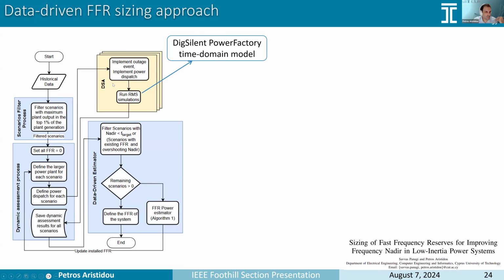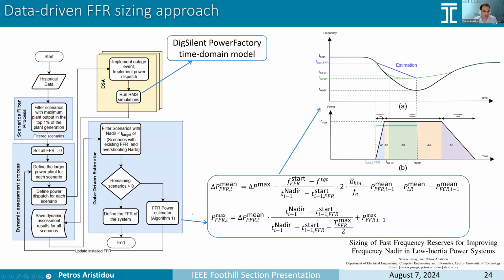So a dynamic security assessment tool based on a DIgSILENT PowerFactory time domain model was used to find which of these scenarios had a problem. And then we use the estimator here, which does a linear estimation to find the amount of fast frequency reserve power that is needed to push the nadir from the simulated value to the target value, which in our case is 49 hertz. But of course, because this is a linear estimation, this is an iterative algorithm that continues to correct the value until we reach this point.